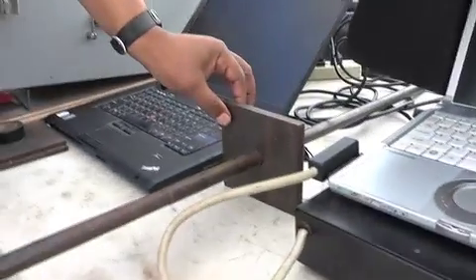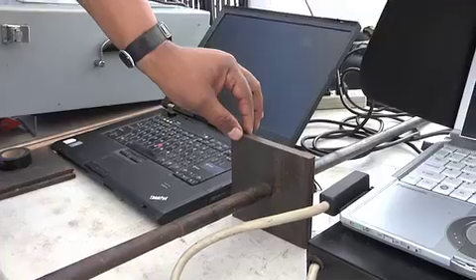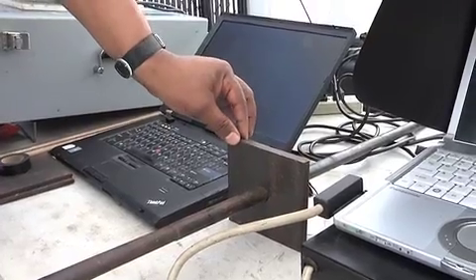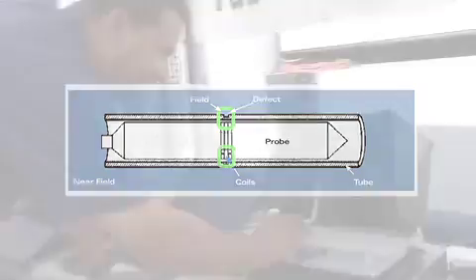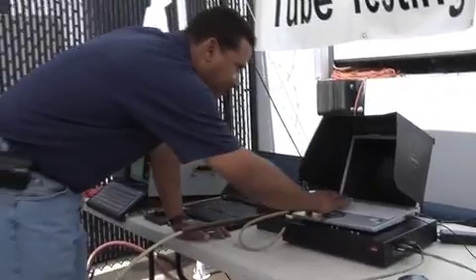The near-field is not seeing the baffle plate at all. The defect underneath that baffle creates a little amplitude difference, but you're still able to identify the 360-degree groove.